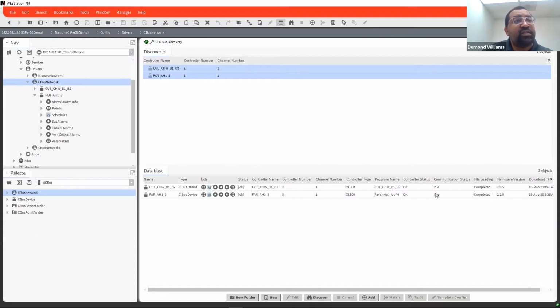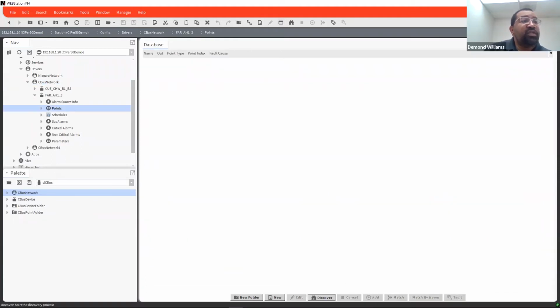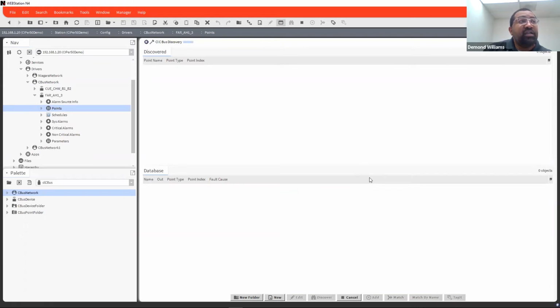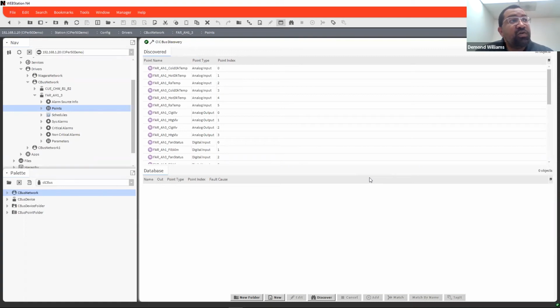So right now, as you can see, my communication status has gone to idle. That means that it has finished pulling in all the information, discovering everything from the controller. So when we go here to our data points, and then we do a discover, it's basically just gonna discover all the points in that controller. So like you said, if it's more than one air handling unit in there, you will actually have to create separate folders for it if you want to relativize your graphics and things like that.